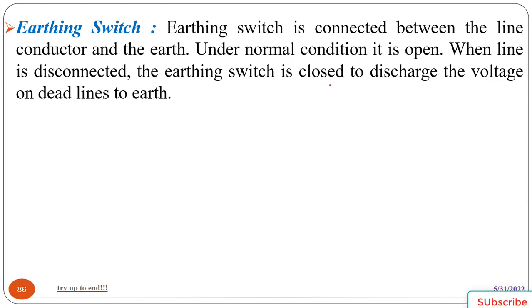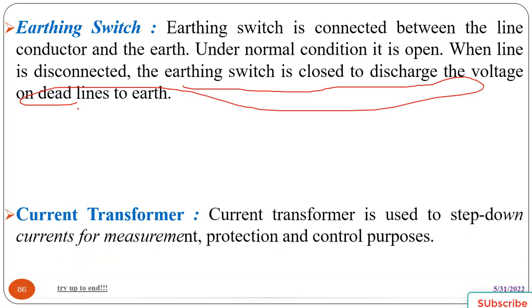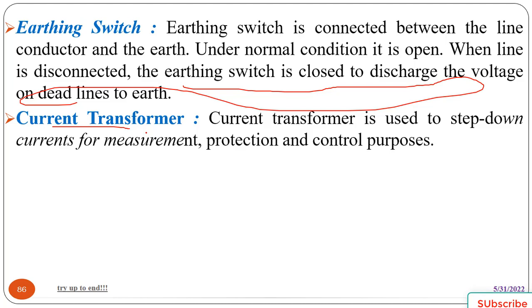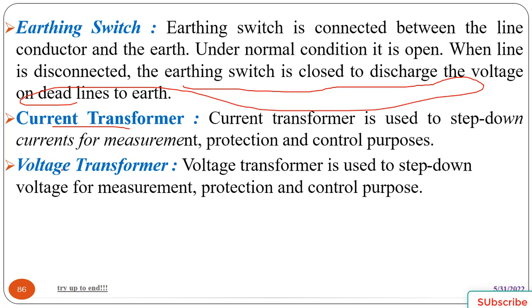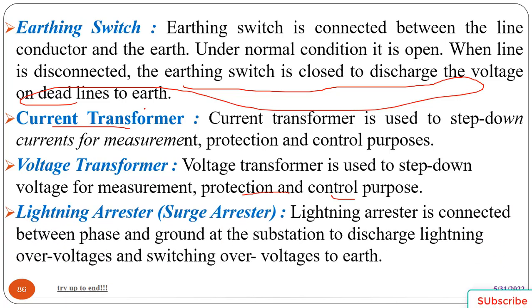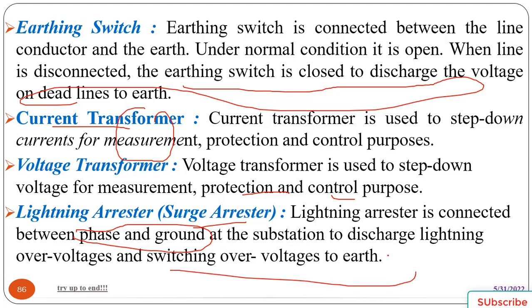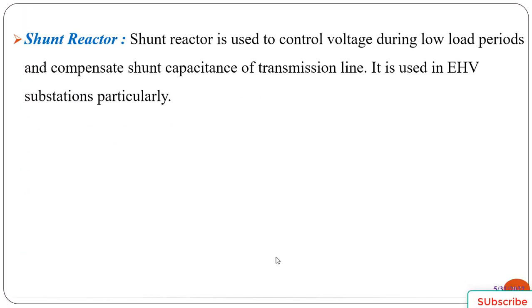The earthing switch is connected between the line conductor and earth. Under normal condition it is open. When the line is disconnected, the earthing switch is closed to discharge the voltage. The current transformer is used to step down current for measurement, protection and control purposes, and the other is the voltage or potential transformer. The voltage transformer is used to step down voltage for measurement, protection and control, like the current transformer. These two transformers are called instrument transformers. The other is the lightning arrestor, or surge arrestor, which is connected between phase and ground at the substation to divert lightning overvoltage and switching overvoltage to earth.